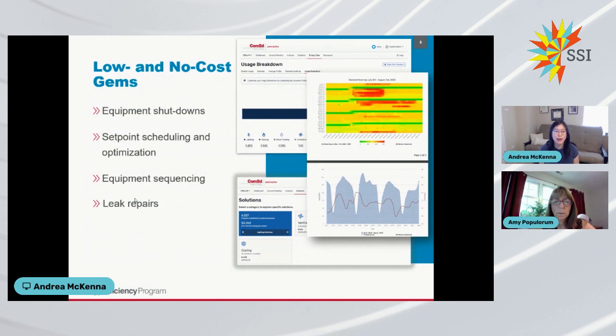Here are some categories of low and no cost EE measures we looked at. For example, shutting down equipment—turning off lighting in unoccupied areas or shutting down idle process equipment. We had set point scheduling and optimization, such as thermostat scheduling in office areas or chilled water temperature resets for chillers. Equipment sequencing, like optimizing air compressor sequencing or condenser pump and fan sequencing for central refrigeration systems. And finally, leak repairs, whether in compressed air systems or vacuum systems.